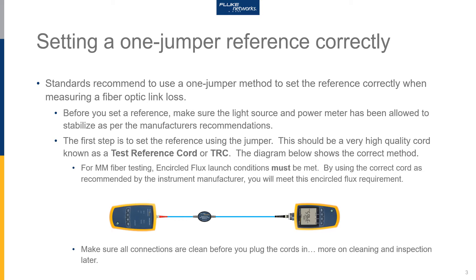As you can see here in our diagram, our source output is connected to our power meter input using a test reference cord. The input connector on the power meter should be the same as the connectors used in the system under test — so if you've got LCs, you need an LC adapter; if you're testing SC terminated fibers, you need an SC connector. But before you connect anything, make sure you inspect and clean, if necessary, all the connections, including the instrument ports and the test reference cord connectors.